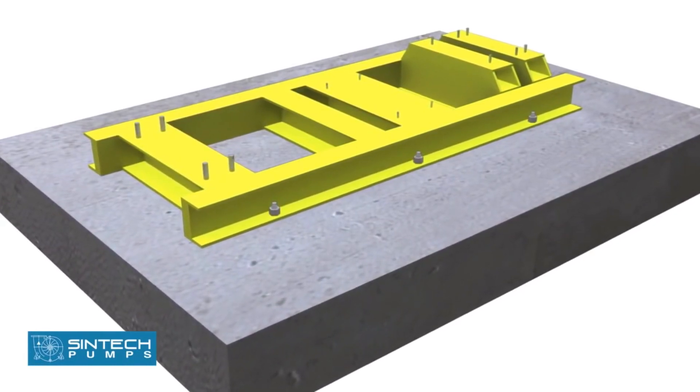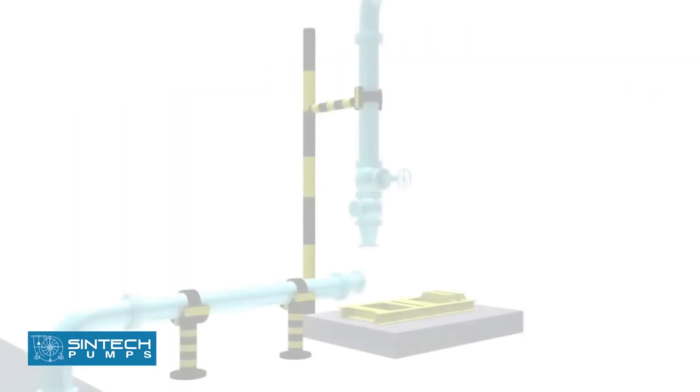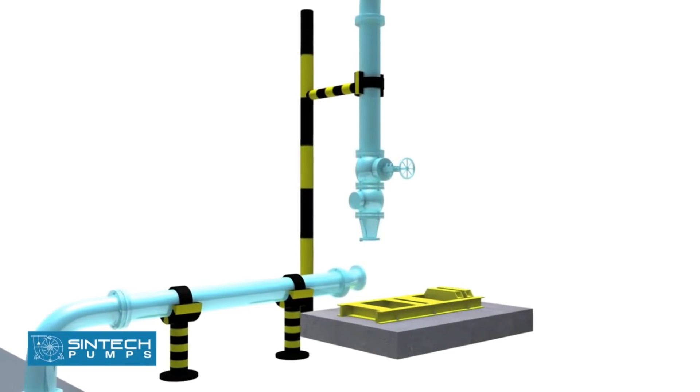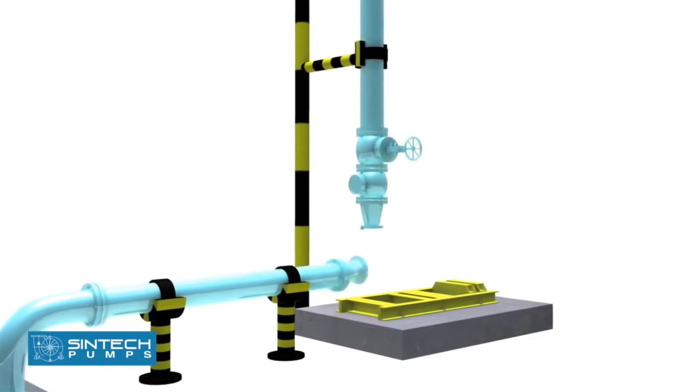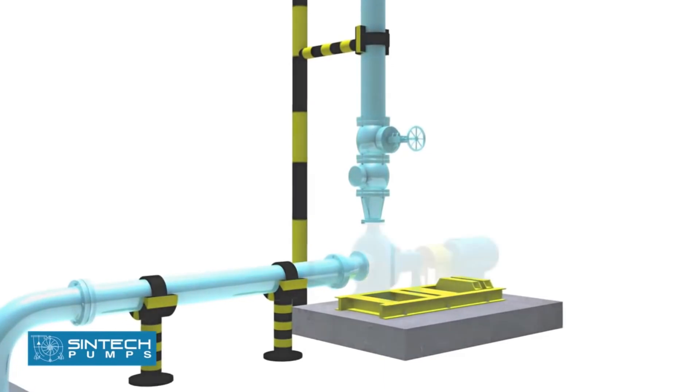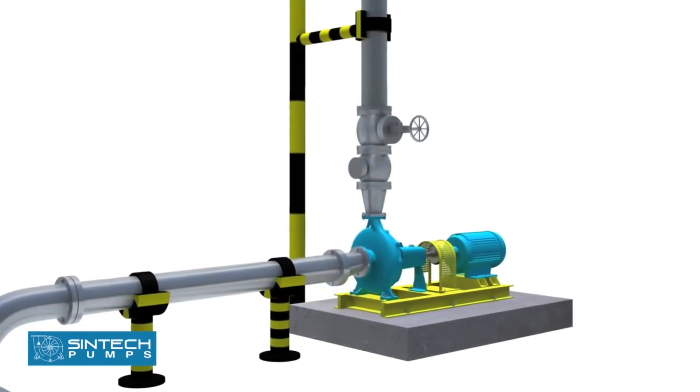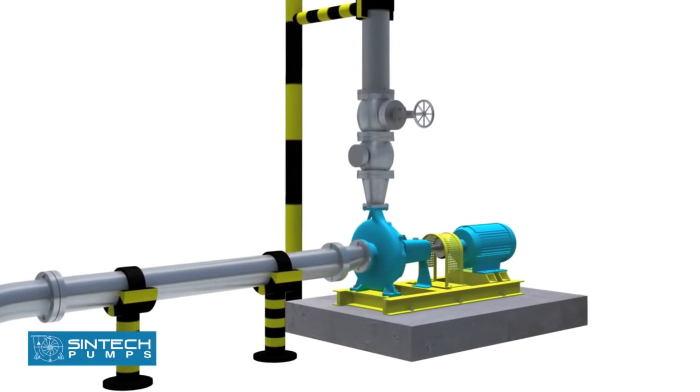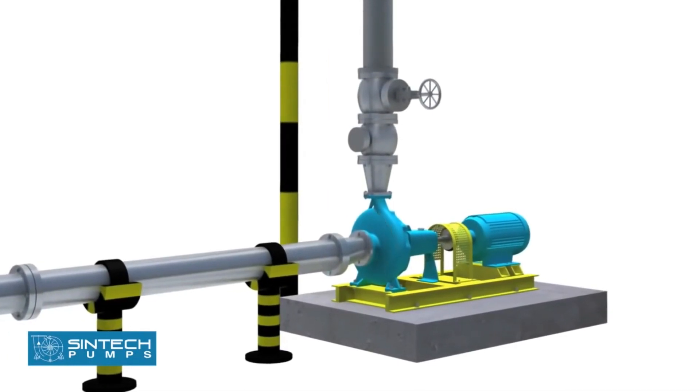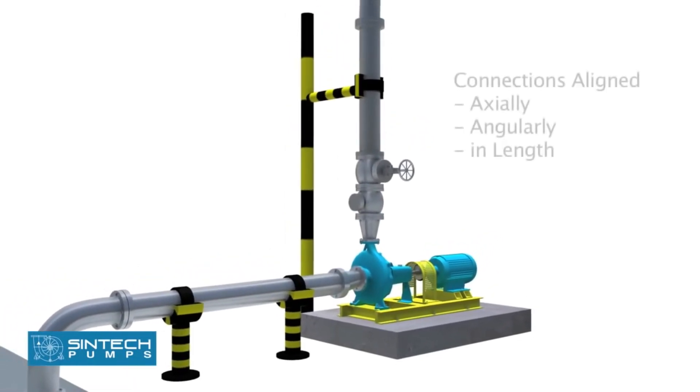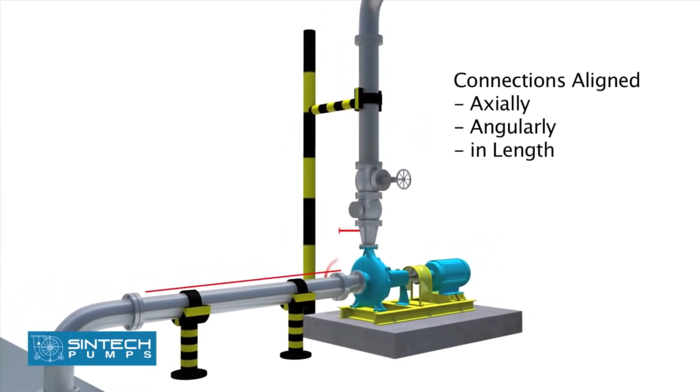Piping associated with the pump must be anchored and supported independently of the pump and should never put any strain on the pump casing. When the pipes are not supported, their weight is borne by the pump casing and may cause them to crack or deflect. It is important that the connections be carefully aligned axially, angularly, and in length.